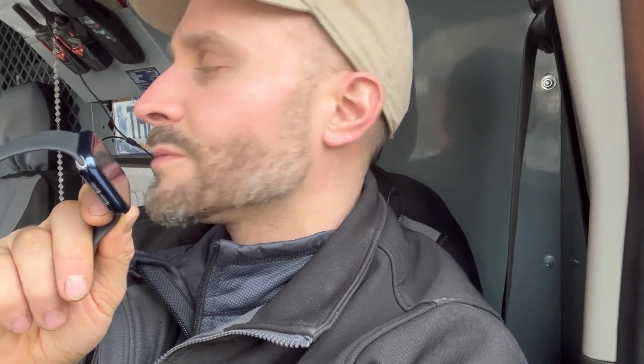Definitely related. And this boiler's never been serviced. No sensors were ever changed, no supply temp sensors were ever changed, nothing was ever changed. The corrosion just built up in this thing. And mind you, the venting outside, the separation between the flue exhaust and the fresh air intake, they're basically touching each other.